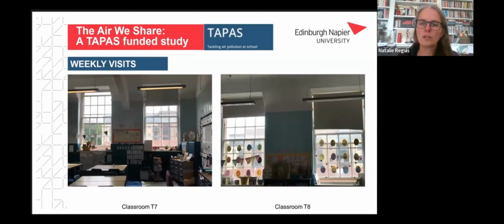Other teachers didn't put this ventilation strategy into practice, as the picture on the right shows, where only the bottom panes were open. Other teachers in classrooms T2 and T3 did say they kept the upper pane open all the time and used the visual sensors to decide when to open the bottom panes. This helped keep the CO2 concentrations low with a more acceptable indoor temperature. These findings and observations show the importance of understanding how to ventilate properly and how to use visual sensors accordingly.